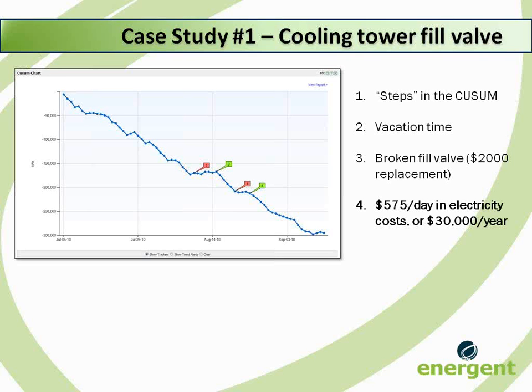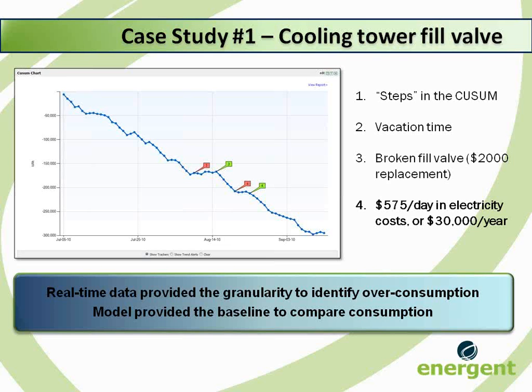The extra electricity was costing the hospital approximately $600 a day that the operator was not on site. Extrapolating that out, assuming the operator works about 260 days a year and half of those the hospital is cooling, that's 55 days at $575 per day that the cooling tower would be over-consuming electricity. That means it would have cost the hospital over $30,000 a year in extra electricity costs.